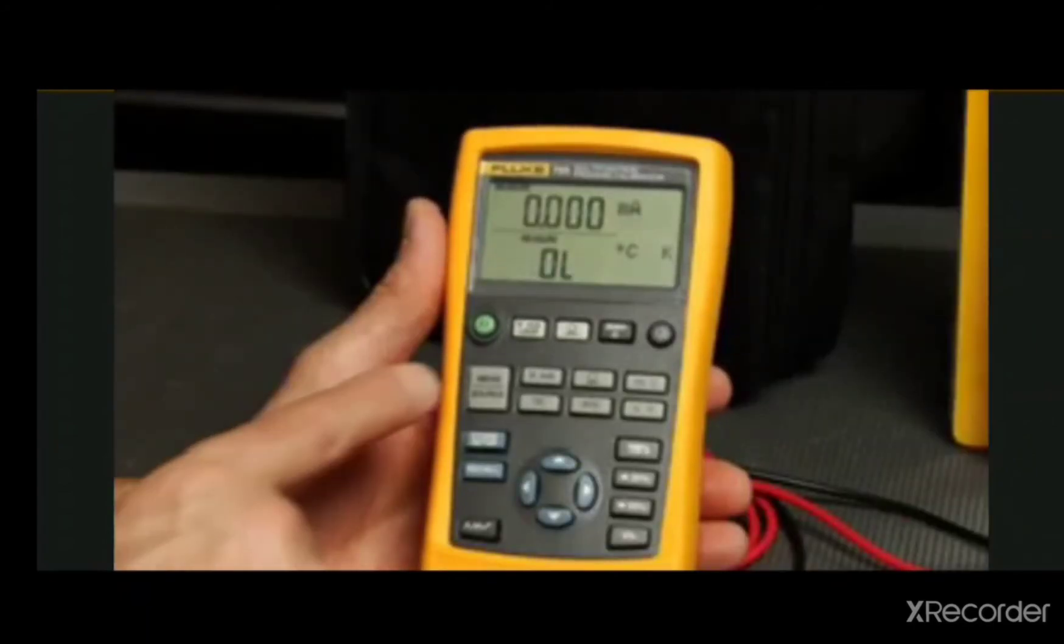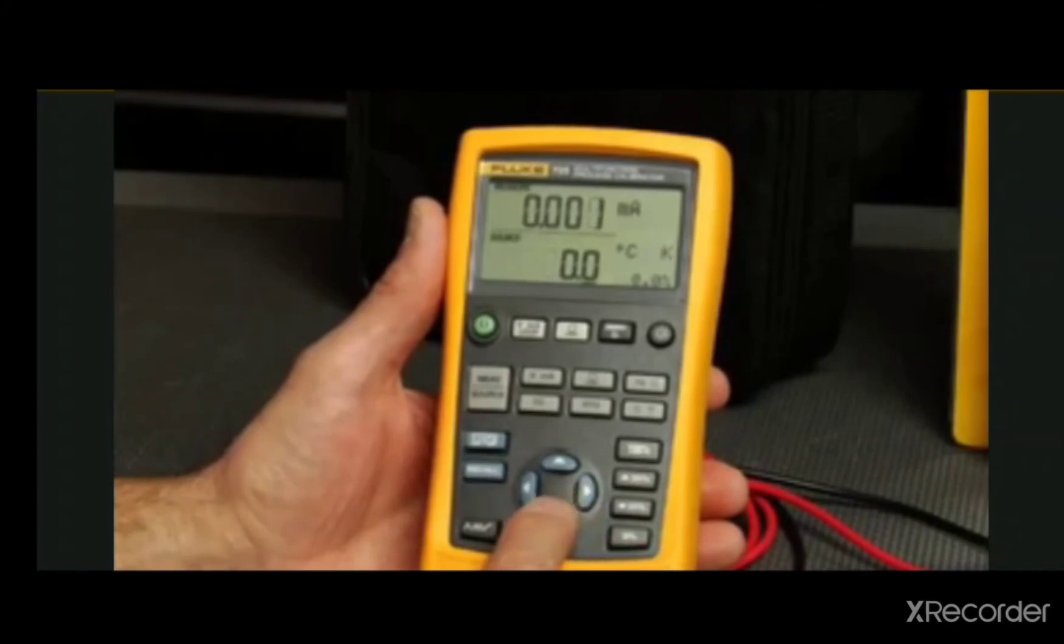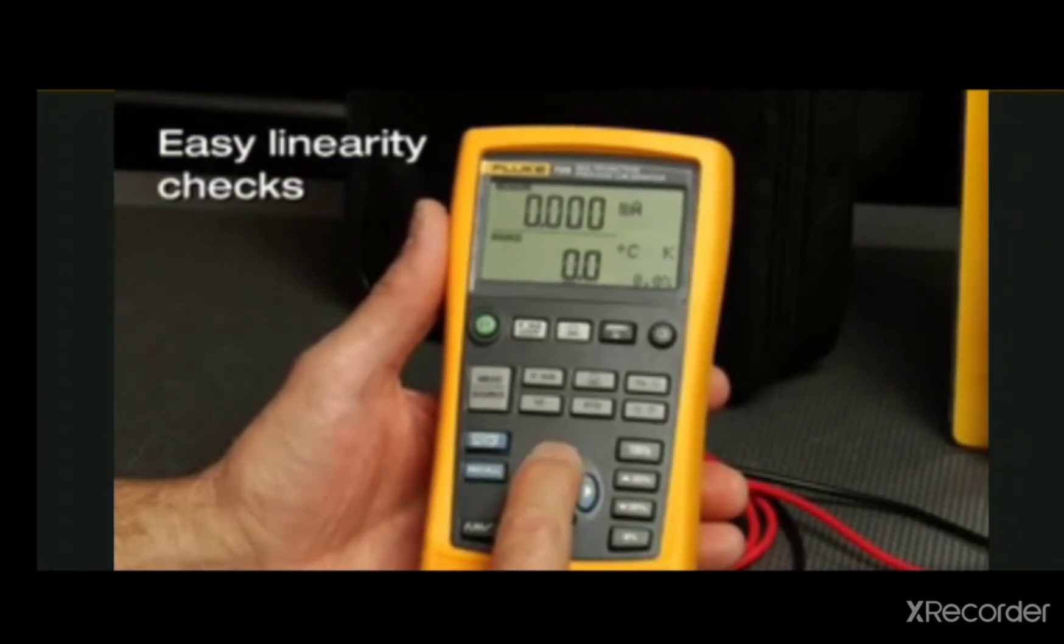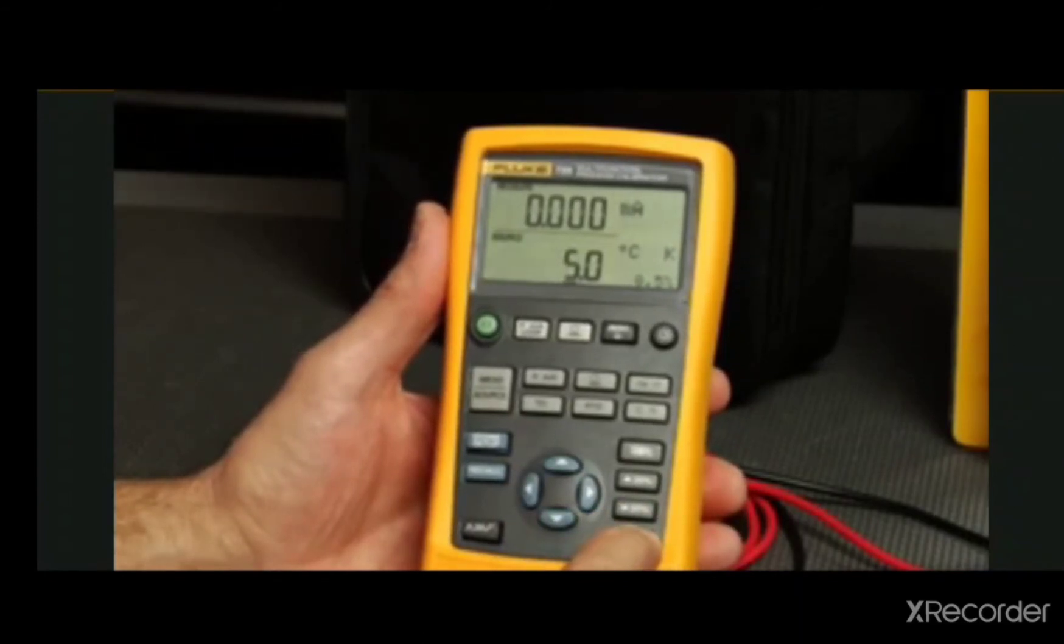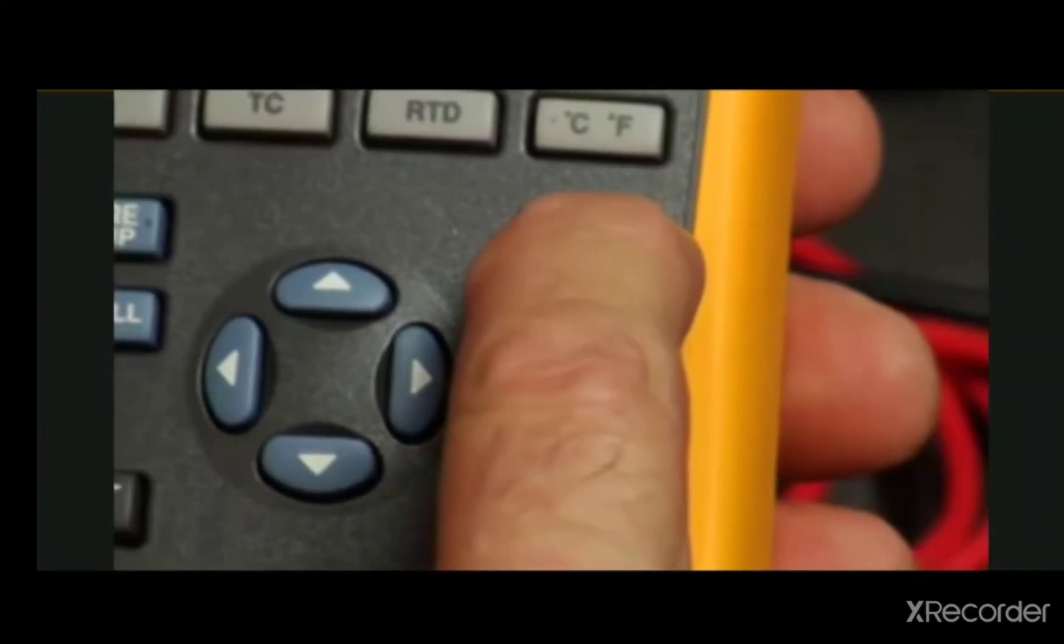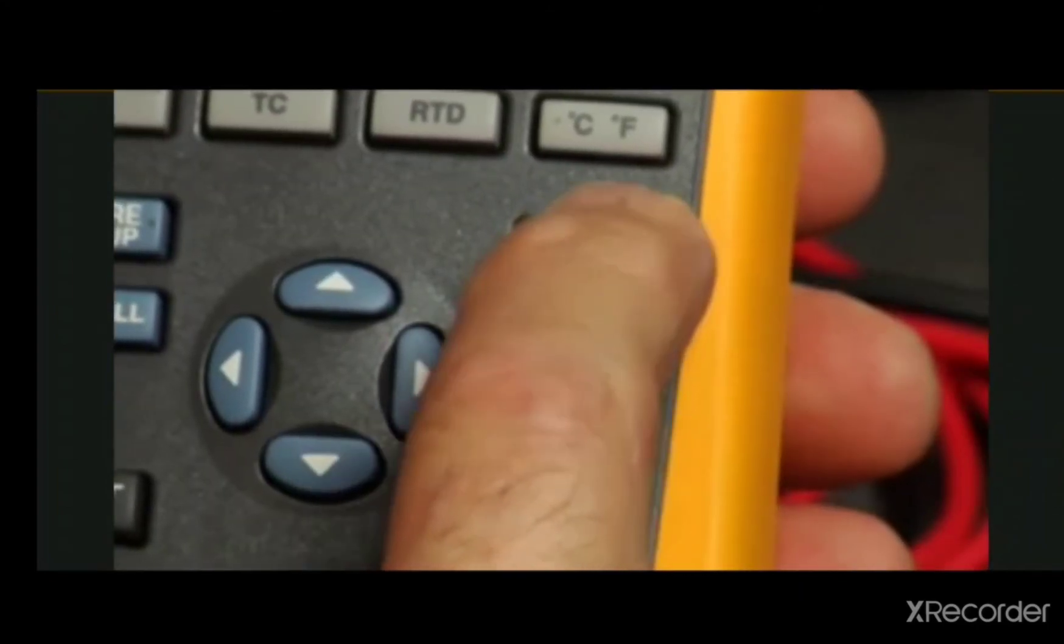You can set the 725 up with zero and span settings to coincide with the transmitter you are testing for easy linearity checks. To do so, first set the calibrator to source the desired 0% output value, then press and hold the 0% button until the display flashes. Set the source then to the desired span value, press and hold the 100% button until the display flashes again.